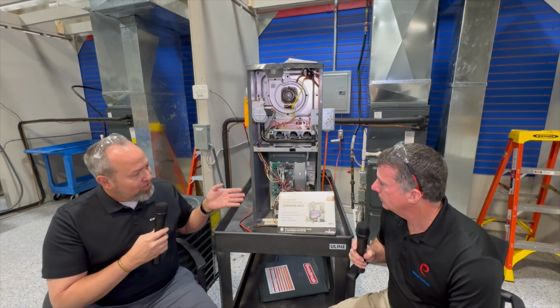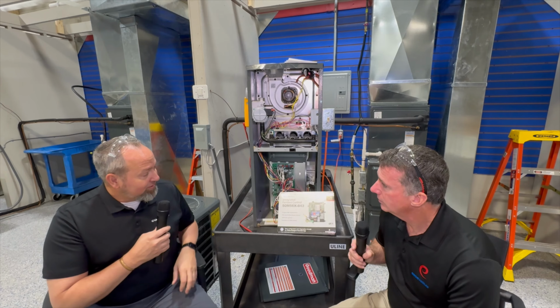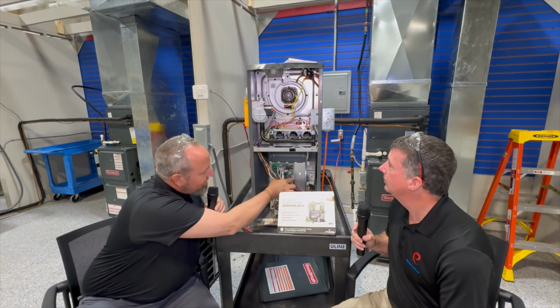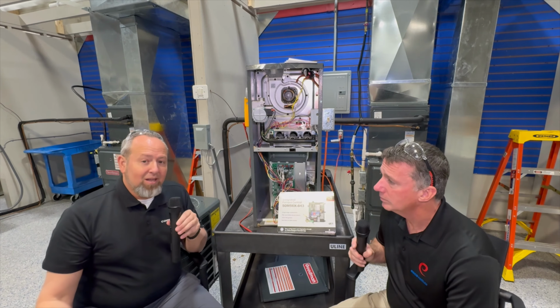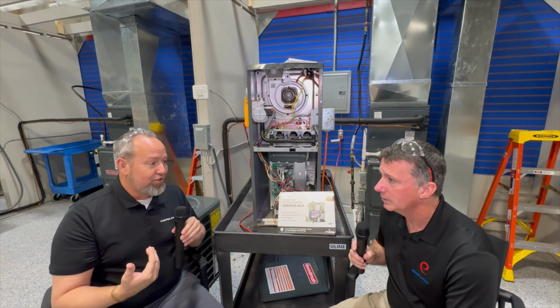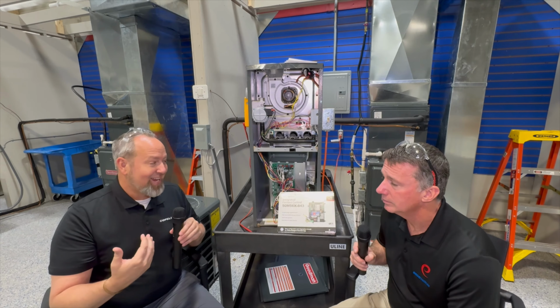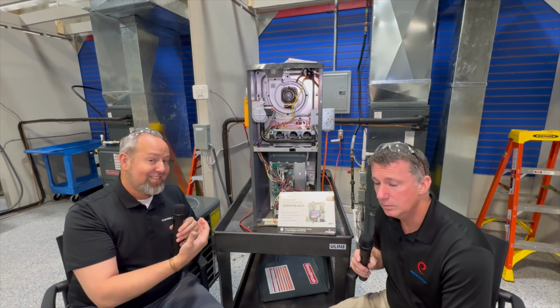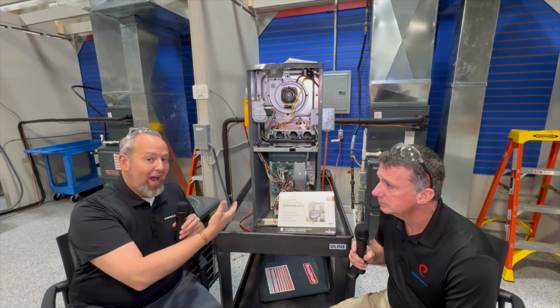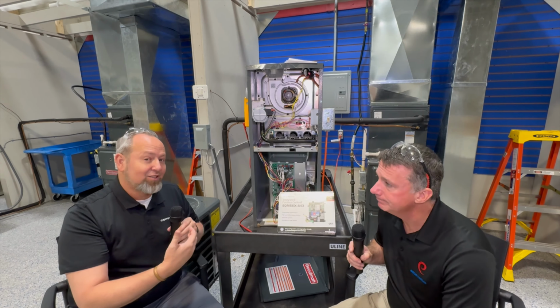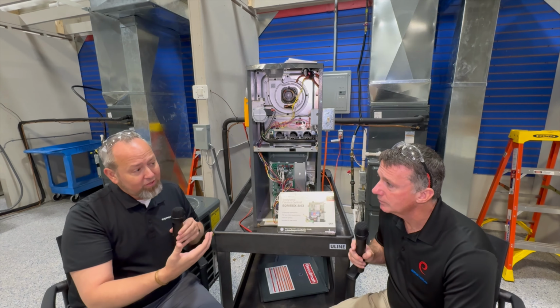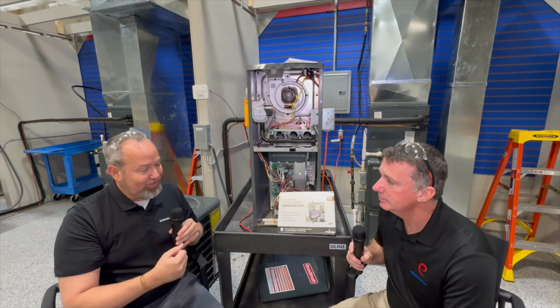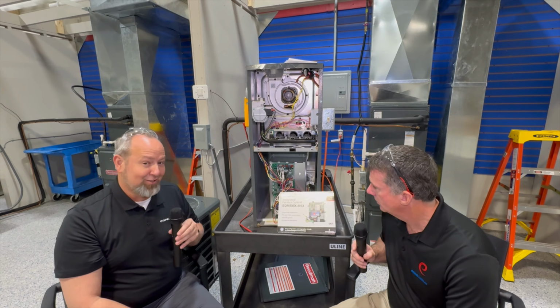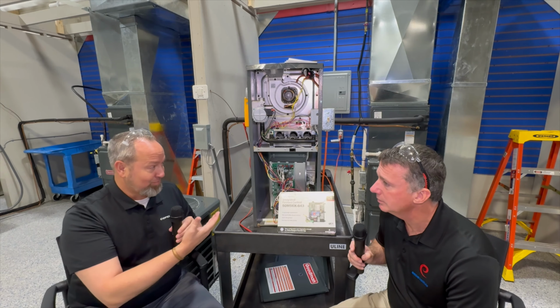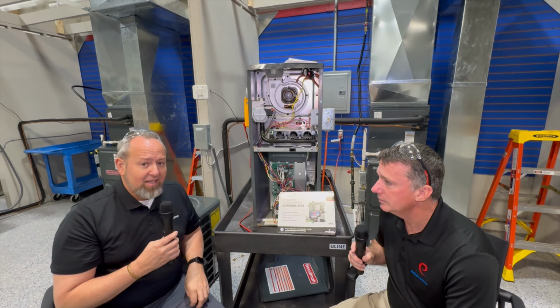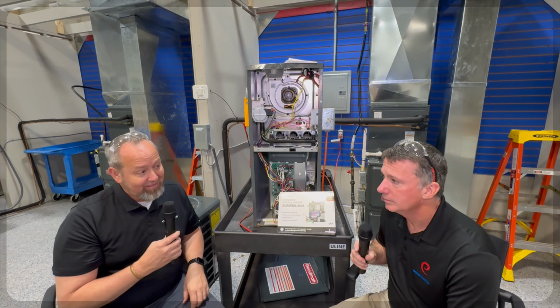What we have today here on this furnace is a Goodman gas furnace, and it has this actual 6-pin inline plug that plugs the ECMx directly into it. One of the things we want to go through today in doing a board replacement is to actually check the voltage signal out of the old board, so we can see if it's 24-volt or, as most of them are, somewhere around 9 to 10 volt DC. So that's what we're looking at here today, to show you that this board with this inline plug is more than likely a 9-volt DC signal.